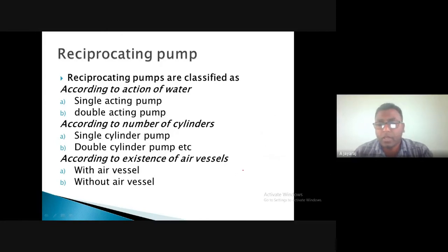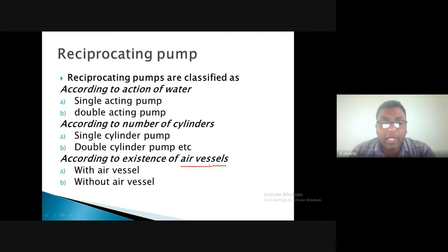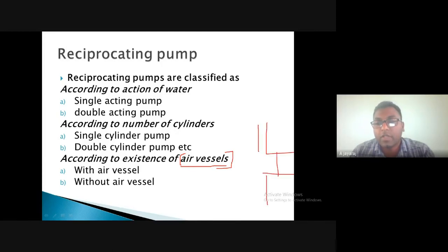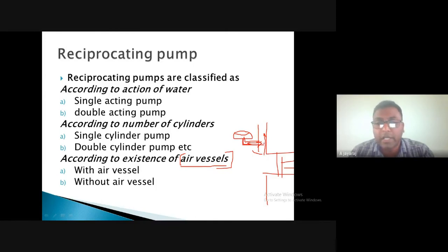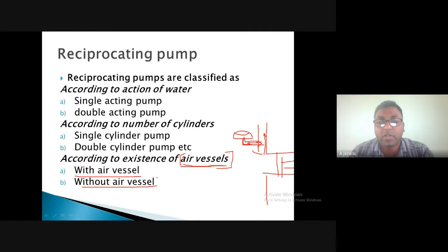Air vessels are smaller chambers attached at the inlet or, more commonly, at the exit side of the reciprocating pump to reduce pressure variation. They contain compressed air separated by a diaphragm. When fluid is supplied at higher pressure, the air vessel absorbs some pressure, reducing shock and pressure surges on the delivery side. When pressure drops, the air vessel compensates by supplying back the higher-pressure fluid stored in it.